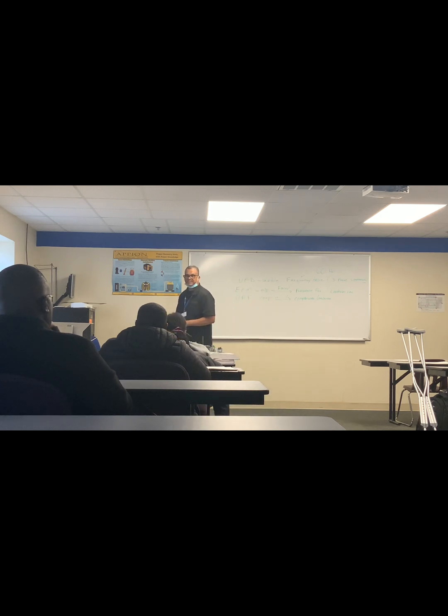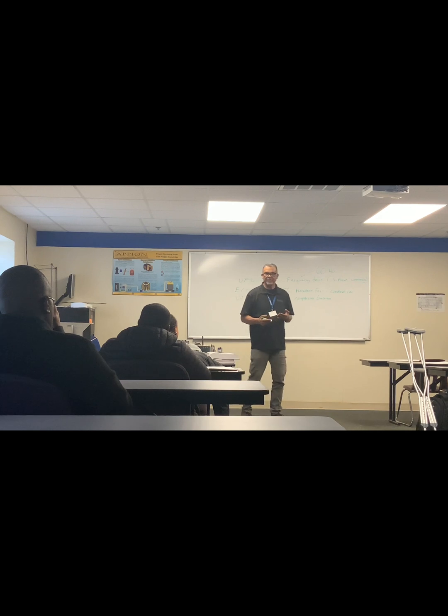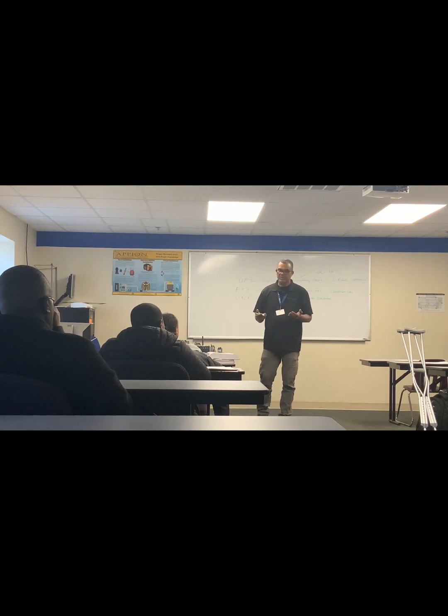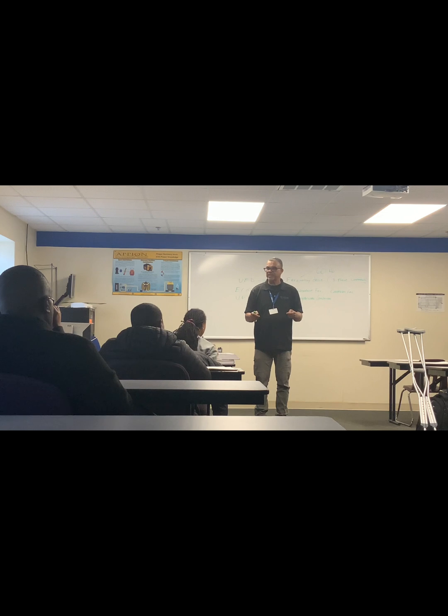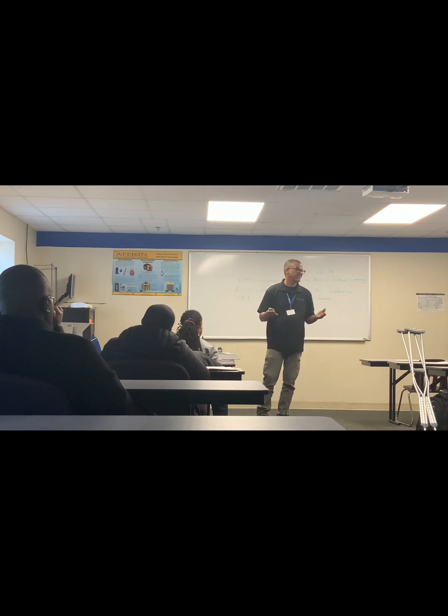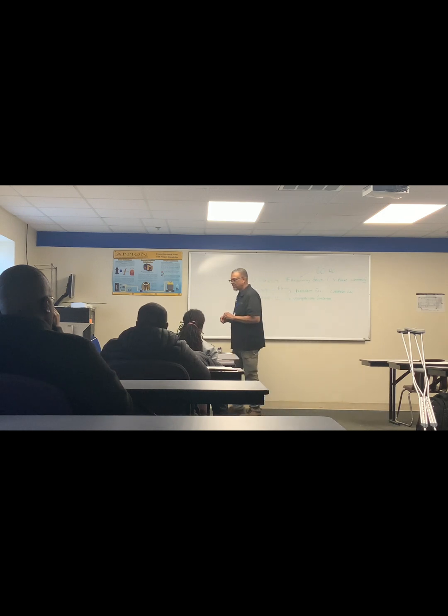When we get to a call, we're gonna read the motor, so it doesn't matter what type of motor it is, we're gonna read it and have the information on it, correct? If something's failed on the motor, you'll have to take the motor out, and it's usually in a band or mounted on the condenser from the top with 4 bolts. You have to remove it. Sometimes you don't have to remove it to get the information. Cell phones have made some of that pretty easy for us. But you have to know several things about a motor. That's what I'm trying to get at.